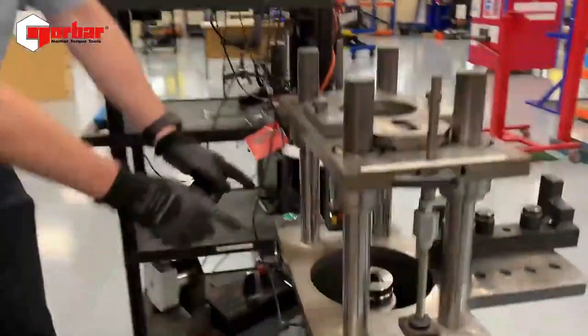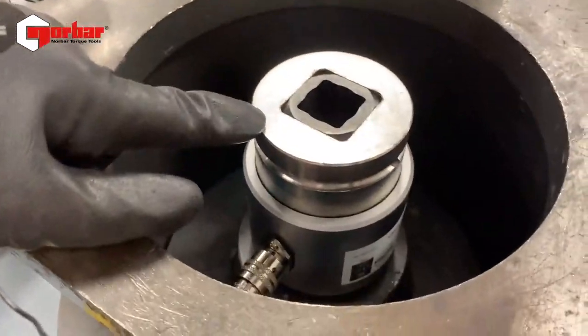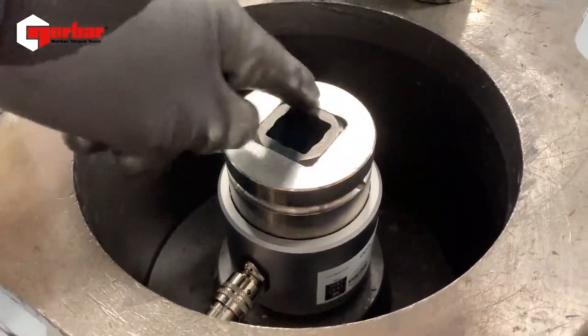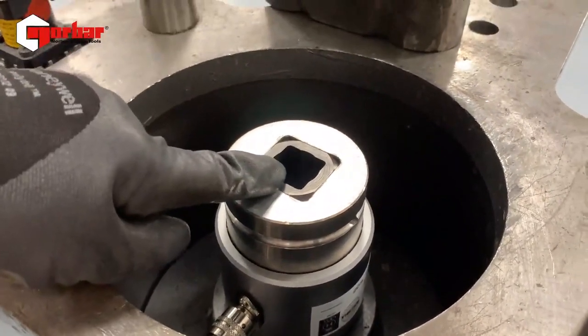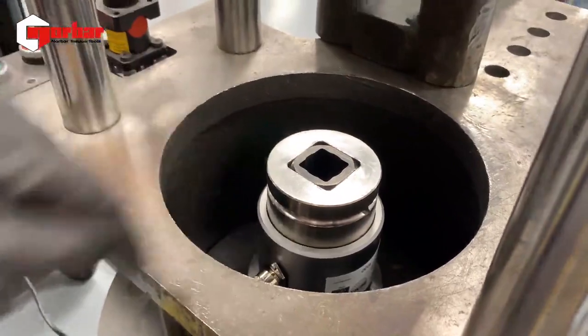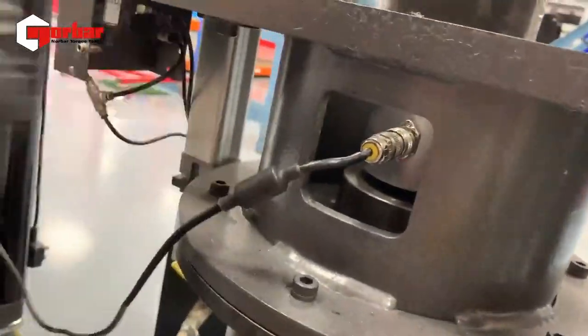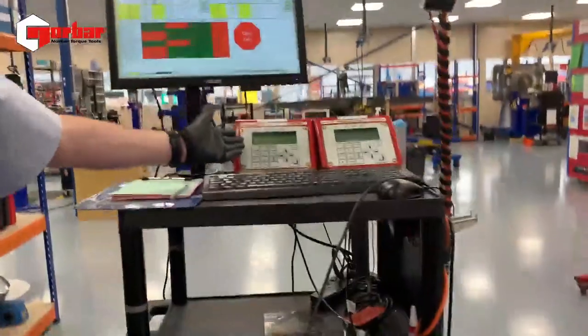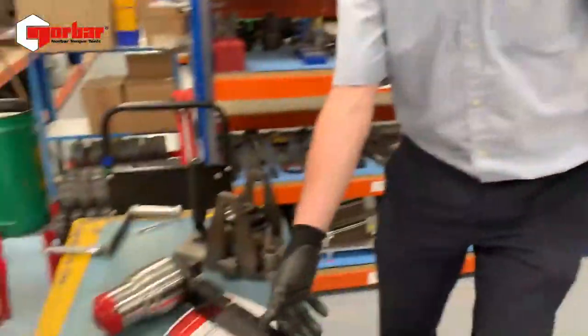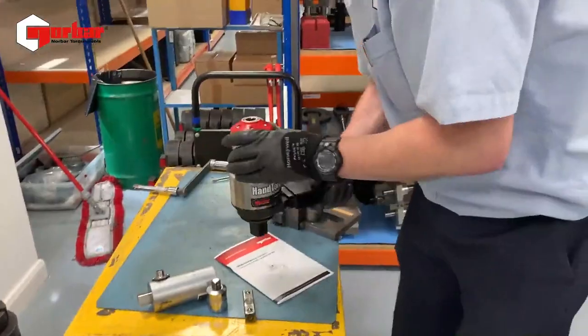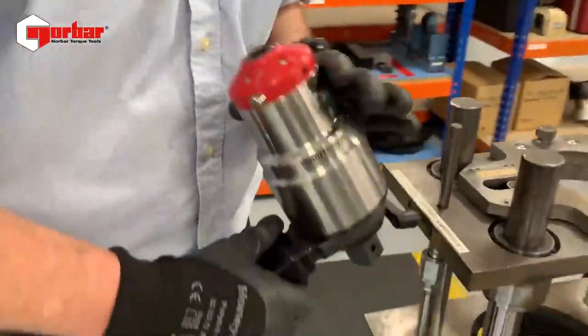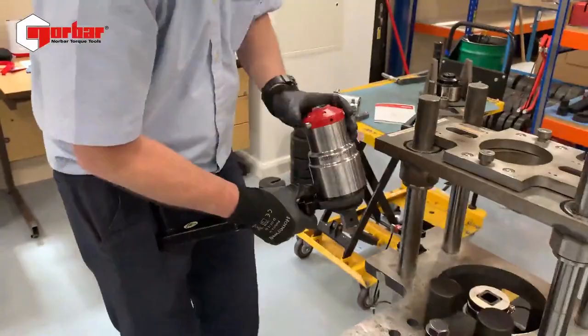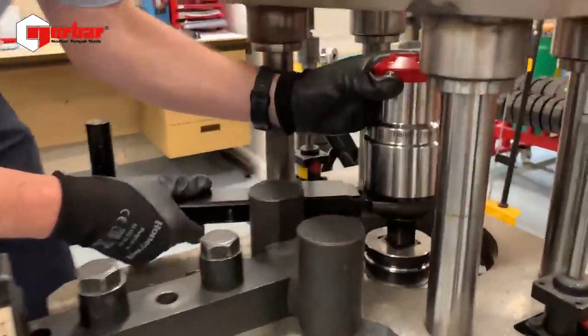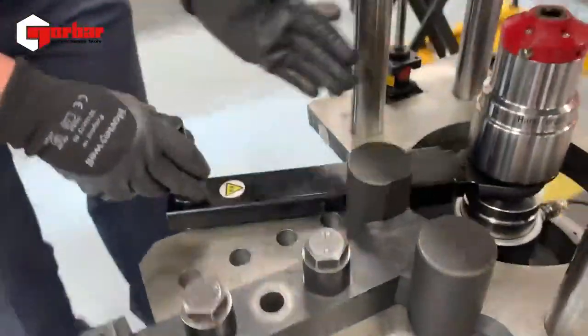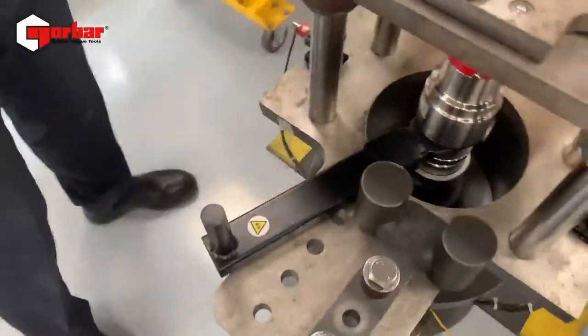So if we can just place the camera down here, I've installed our 4000 transducer. I've also installed a 1.5 inch to 1 inch drive adapter. This is because my HandTorque has a 1 inch output. Okay, I've already connected this to the TTT, which I'm using as a display device over here. Okay, so I'm now going to drop my HandTorque into the rig, and what I've already done, just to make my life a little bit easier, is turn the input so that my square drive drops in and sits nicely on a reaction point. Okay, so that's our HandTorque dropped in.